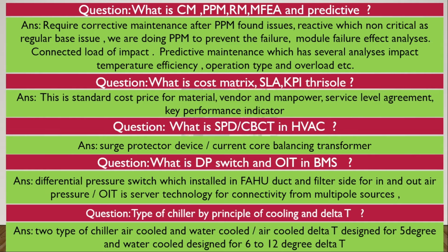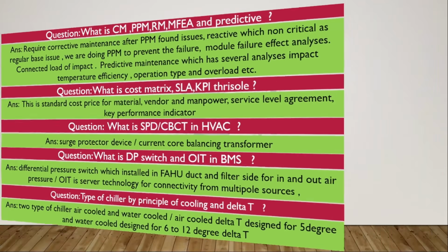This is the required IoT. Question: type of chiller by principle of cooling and delta T. So two types of chiller, air cooled and water cooled. Air cooled is designed for 5 degree delta T and water cooled is designed for 6 to 12 degree delta T.